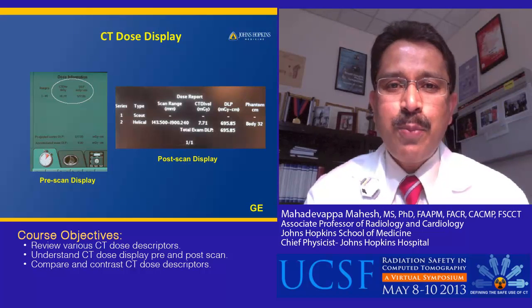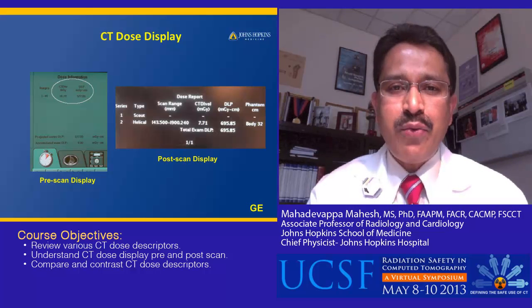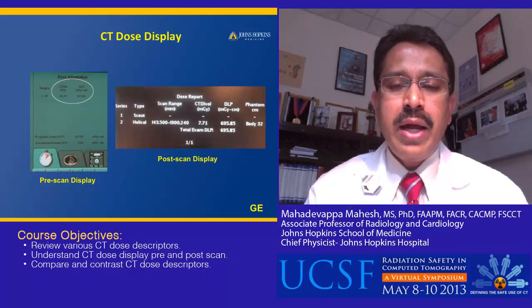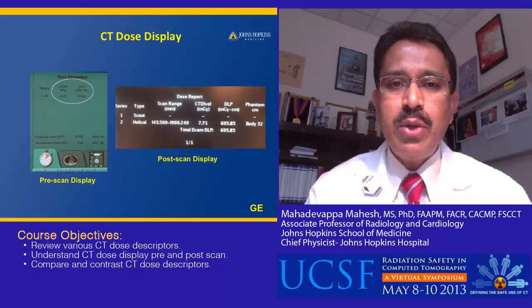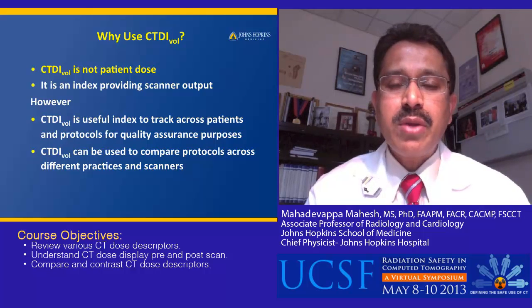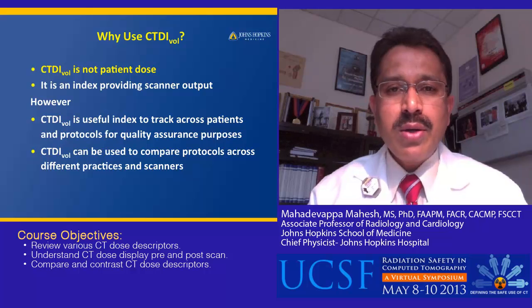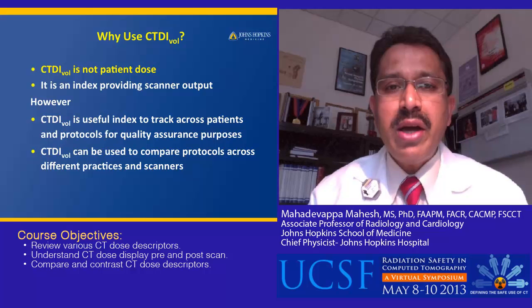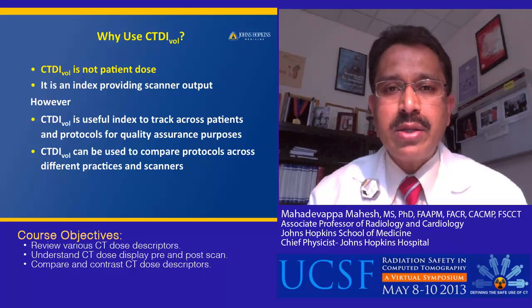As seen in the preceding slides, the post-scan display or dose reports vary from manufacturer to manufacturer. There are no standard dose displays right now. Even though structured dose reports are slowly becoming available with all manufacturers, the displayed dose information still varies. It is important to understand what these dose displays are based on for each particular manufacturer and also understand some of the limitations. CTDIvol is not patient dose — it is a measure of the radiation output of a particular CT scanner. However, CTDIvol is very helpful in tracking across protocols for quality control purposes and for comparing radiation output for different protocols and settings.